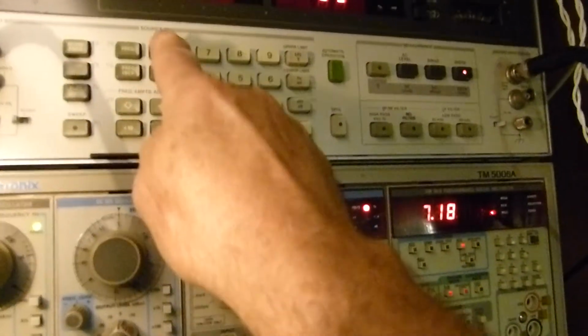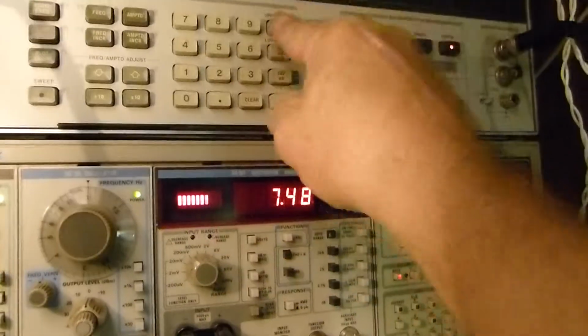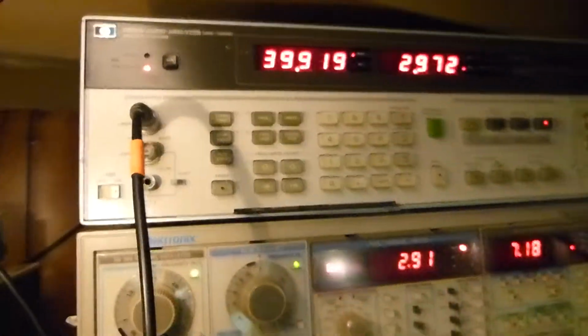If you want to put it back in local mode, you just press this, and then you can change it to whatever you want. Like if I wanted to change the amplitude, I'd put it in local and say amplitude 2 volts. And then when I go back down here to my mouse and click on it again, this light will come back on, and it'll throw it back into remote control mode, and it's controlled by the PC. So there you go.